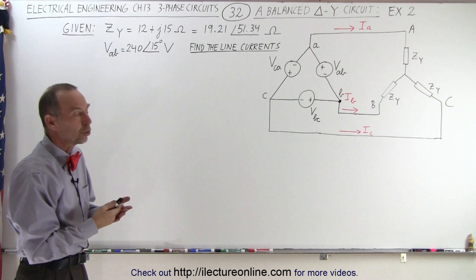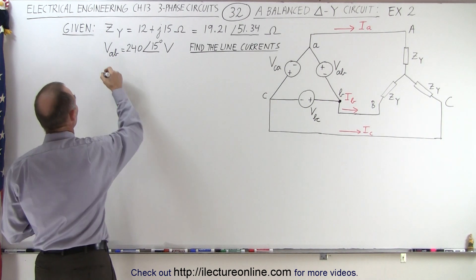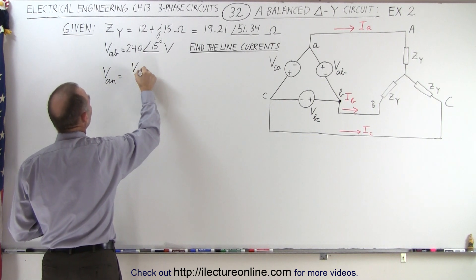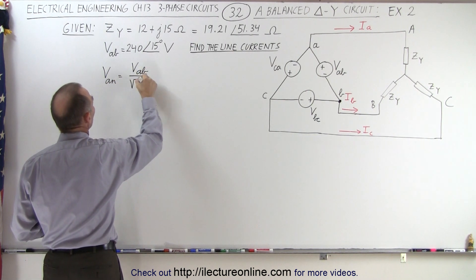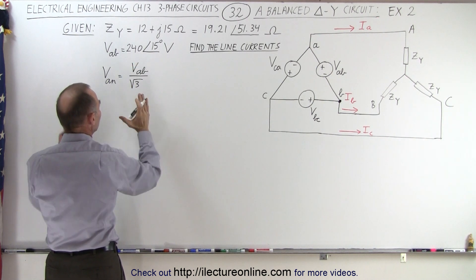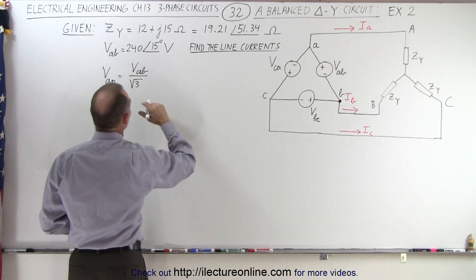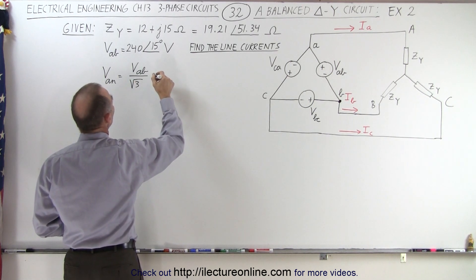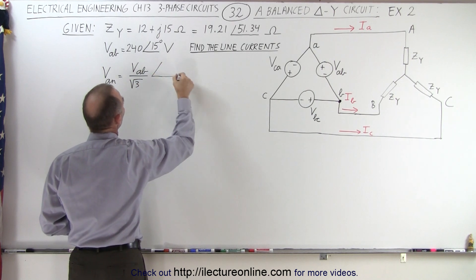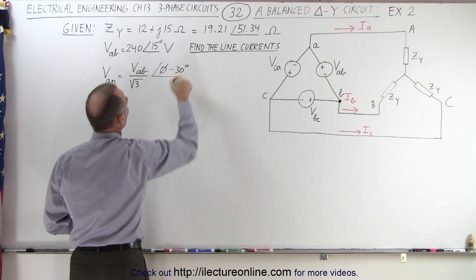Right away what we should do is find the equivalent phase voltage. We know that the phase voltage VAN is equal to VAB divided by the square root of 3. That's the adjustment for the magnitude because the phase voltage is smaller than the line voltage, the equivalent line voltage. And then we have to subtract 30 degrees from the phase angle — whatever phase angle we started with, we subtract 30 degrees from that.